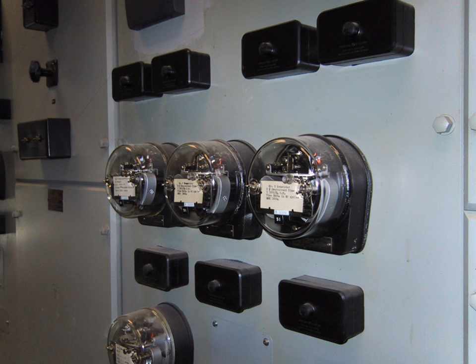Such polarized relays are used on direct current circuits to detect, for example, reverse current into a generator. These relays can be made bistable, maintaining a contact closed with no coil current and requiring reverse current to reset. For AC circuits, the principle is extended with a polarizing winding connected to a reference voltage source. Lightweight contacts make for sensitive relays that operate quickly, but small contacts can't carry or break heavy currents. Often the measuring relay will trigger auxiliary telephone-type armature relays.